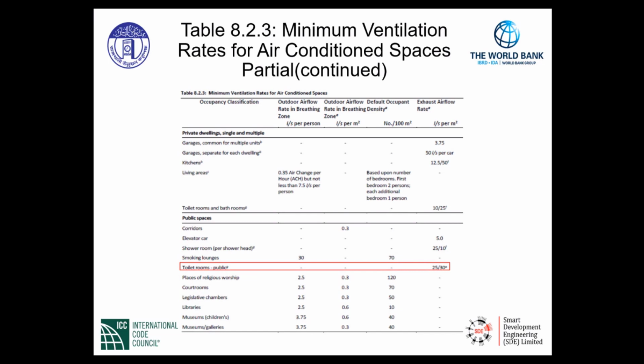Further, if you go to the very last column, the exhaust airflow rate column, there is another note after the values that you see in that particular column. Now, the toilet rooms have a note E after the 30 liter per second requirement. That E is an indicator that the rates are per water closet or urinal. So that higher rate is provided where we have heavy use, such as toilets in theaters, schools, sports facilities, things of that nature. The lower rate is permitted where periods of heavy use are not expected. Therefore, we have a simple way to provide exhaust requirements for our toilet rooms in public spaces.